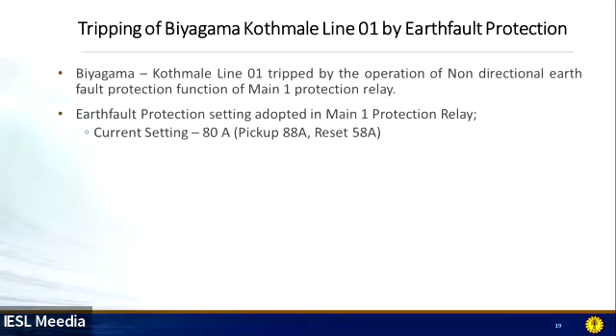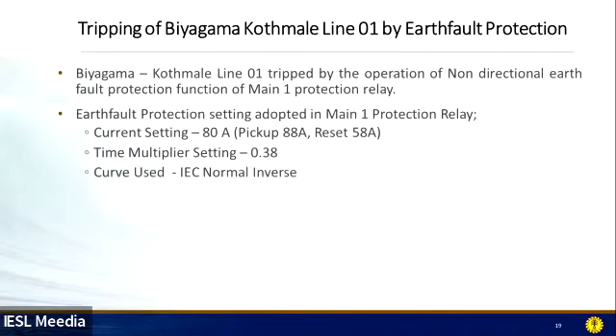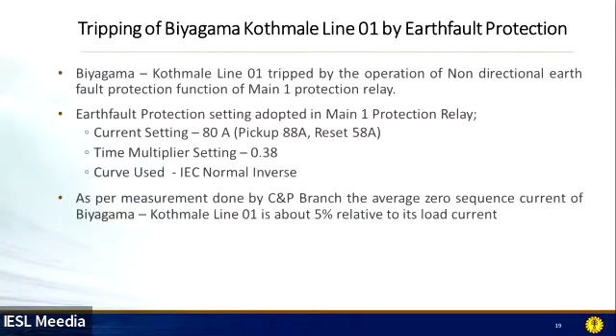So when we analyzed the relay manual and how the relay behaves, we found that when we set small values of current in this particular relay, it keeps about a 30 ampere difference between pickup and reset. In secondary terms, it's about 15 milliampere. The time multiplier setting adopted in this situation is 0.38, and the curve used is IEC normal inverse.